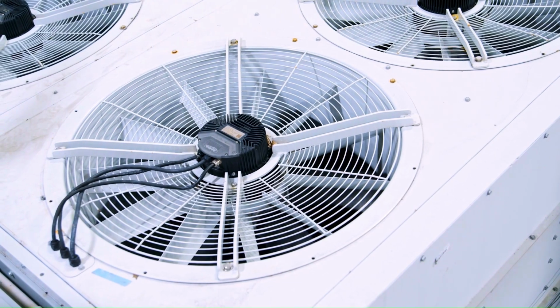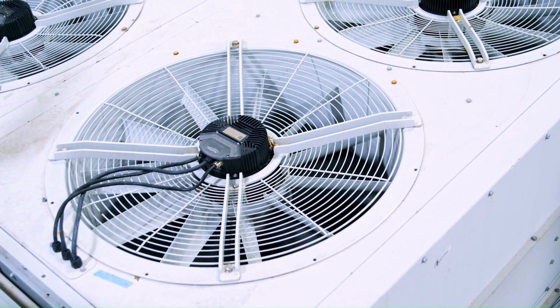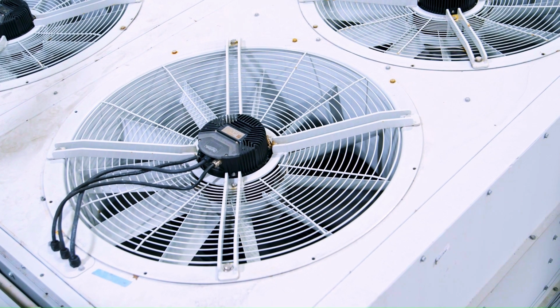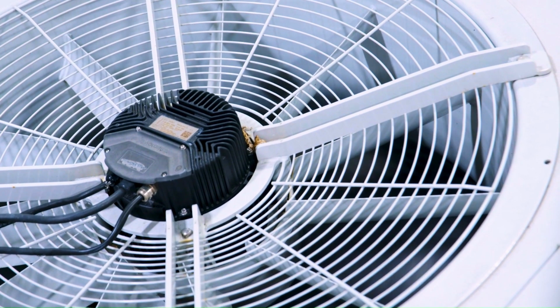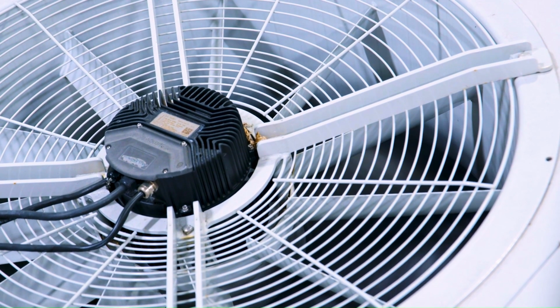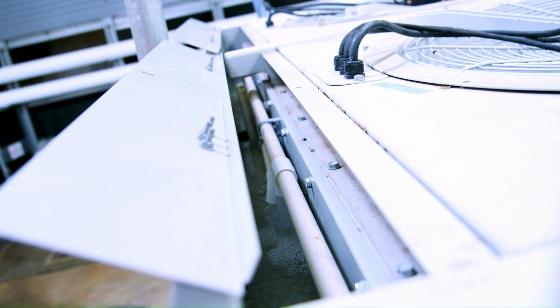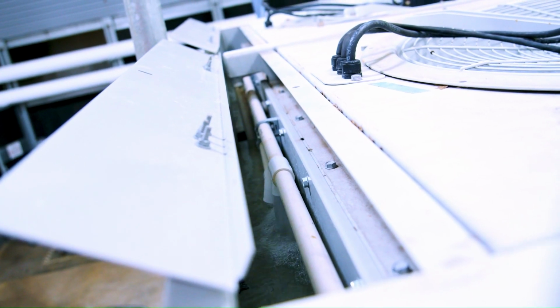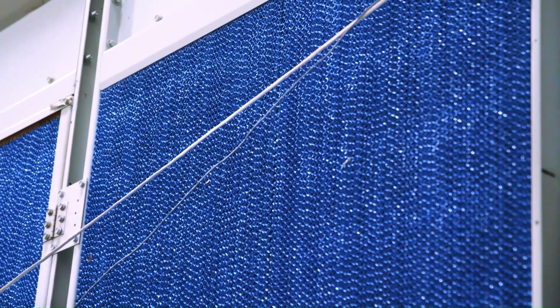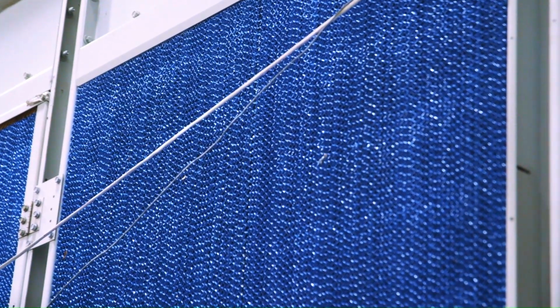It could satisfy the temperature demands of the application while improving system efficiency by allowing the facility to operate in dry cooling mode for up to 90% of the year. Pre-cooling water is introduced only during peak ambient temperature conditions. Even then, it is recirculated, helping minimize water usage, reduce treatment requirements, and lower operating expense. At that point, the team had a compelling system concept. But concepts have to perform.